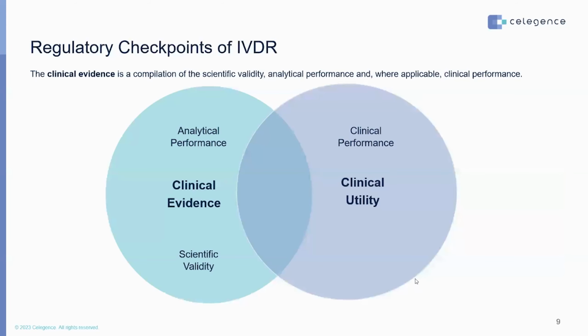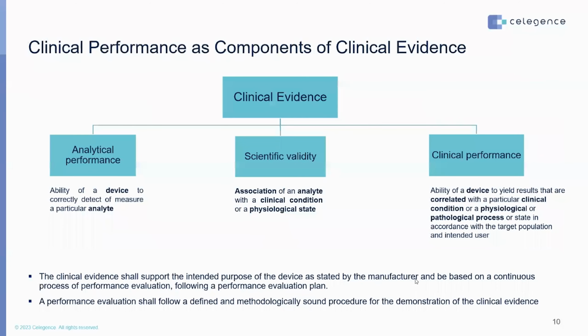So, for a performance evaluation, there are mainly three key points. One is the scientific validity, one is the analytical performance, and the last is the clinical performance. So when we talk about clinical evidence, we talk about providing clinical evidence for all these three components. However, clinical evidence majorly supports the analytical performance and the scientific validity of an IVD, versus the clinical performance is mainly supported by clinical utility. In some scenarios, it is possible to provide clinical evidence to support the clinical performance of an IVD as well. We'll just go over what we mean by the analytical performance, scientific validity, and clinical performance of an IVD.